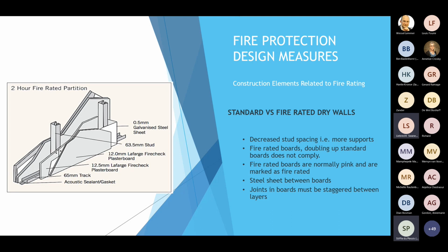But the code of practice has allowed that board to be installed vertically. So this is the point I want to make: the client, the contractors, everybody is using your fire rated wall, which needs to be installed vertically. They use it in certain circumstances horizontally, stating that we will have a fire rating on that panel as installed, which is not the case. It's not approved to be installed horizontally. It's only installed and SABS approved and signed off with installation vertically as discussed. So just make a note of it.